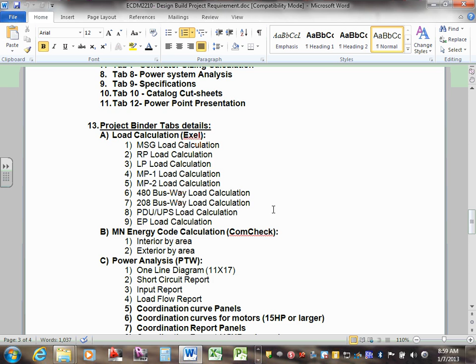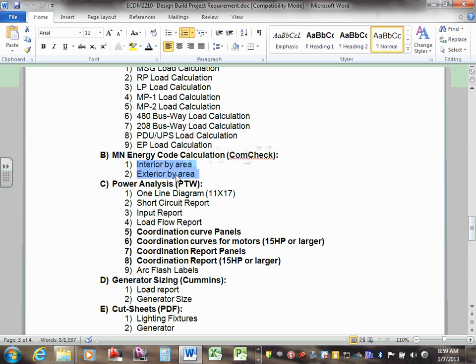Under receptacle panel, what do you add? Receptacles. Lighting panel, lighting. Under bus duct 480, in the mechanical equipment, there's equipment that are connected to bus duct 480. You add them up. The biggest one, you add 25% on it. Done. Really, it looks like a lot of things. It's really not hard. Not hard at all. Minnesota Energy, guys. Remember the reports that you did for interior and exterior? That's what you're going to do now, except we have a 2-story building, and we have the outside.